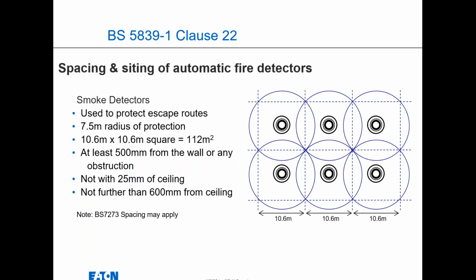When you look at spacing, the design guide that we've given you as a handout will give you all this information in a smaller version. Your smoke detectors have a 7.5 meter radius of protection, so 10.6 by 10.6 square. They should be at least 500 mil away from the wall or any obstruction. They shouldn't be within 25 mil of the ceiling, but that's okay because all manufacturers have that already covered. When you fit it to a ceiling, the base pushes the detector away from the ceiling. So you're not going to be within 25 mil unless you try and flush it, and not further than 600 mil from the ceiling. So you can't be too low.